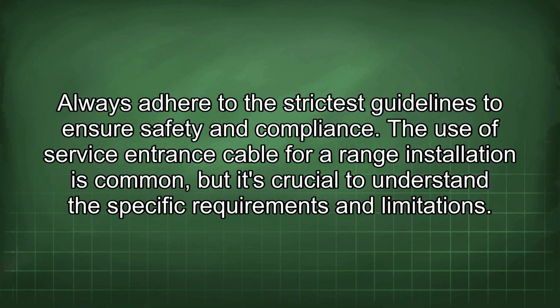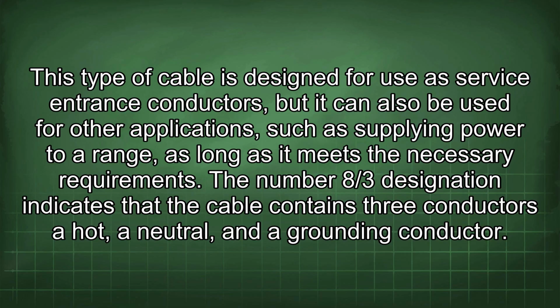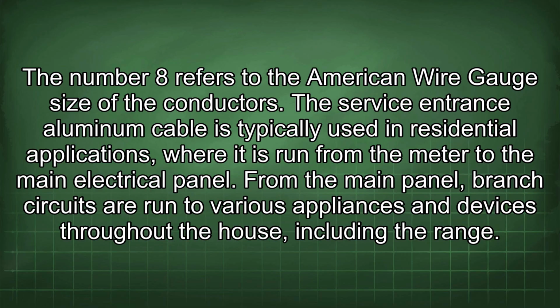The use of service entrance cable for a range installation is common, but it's crucial to understand the specific requirements and limitations. This type of cable is designed for use as service entrance conductors, but it can also be used for other applications, such as supplying power to a range, as long as it meets the necessary requirements. The number 8/3 designation indicates that the cable contains 3 conductors, a hot, a neutral, and a grounding conductor. The number 8 refers to the American wire gauge size of the conductors.